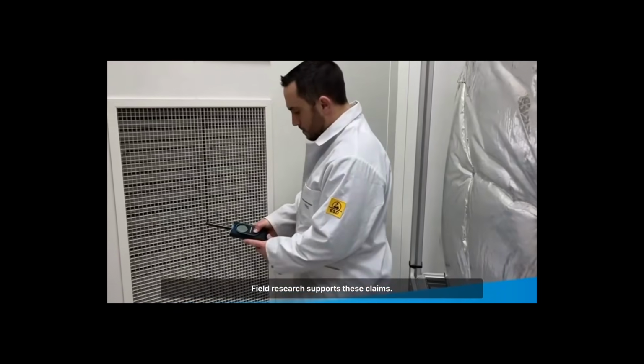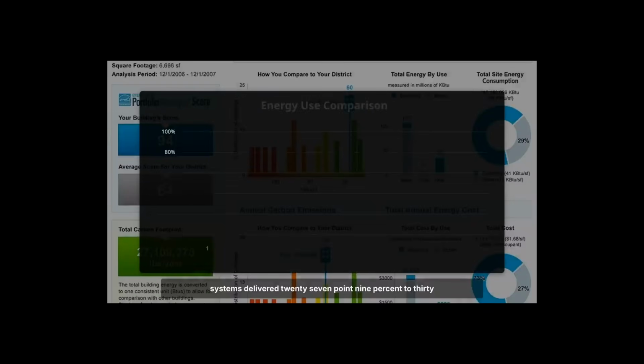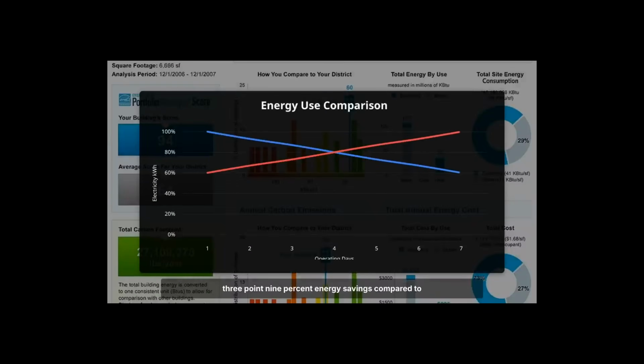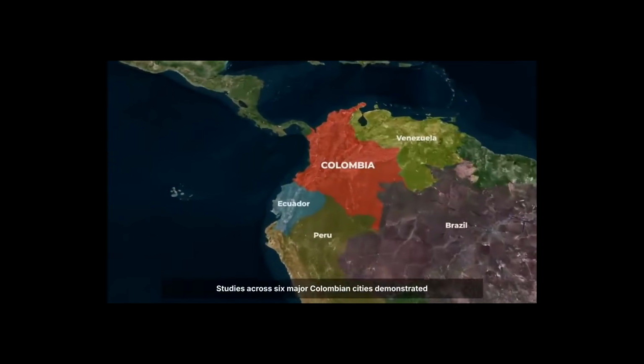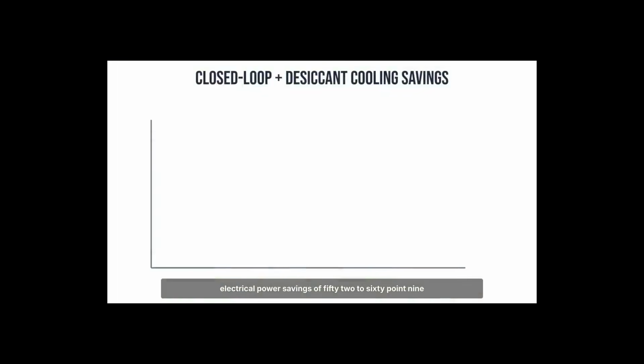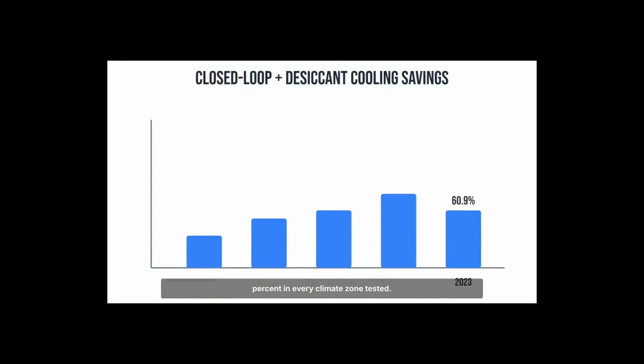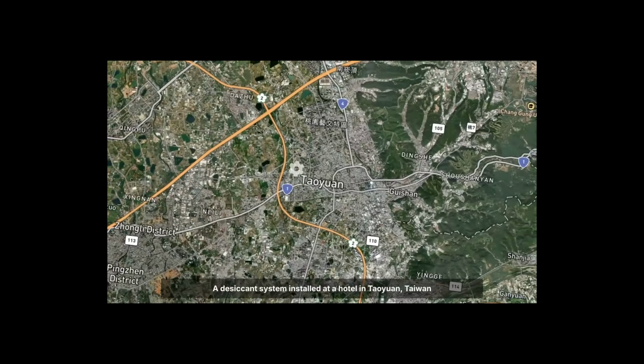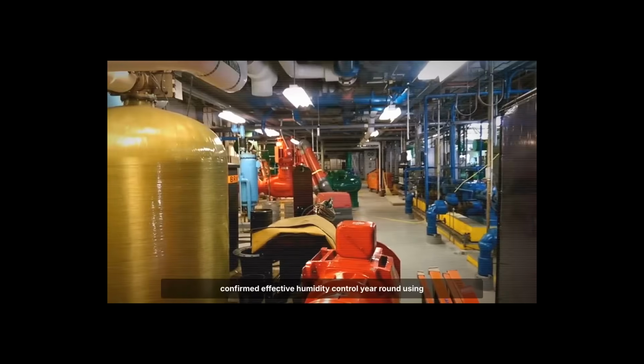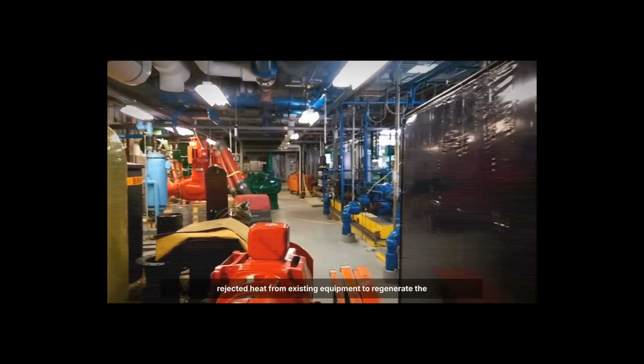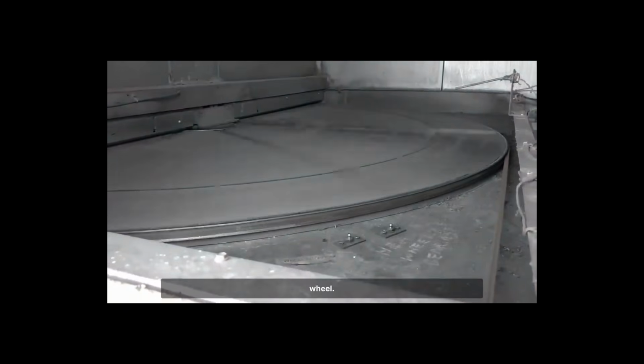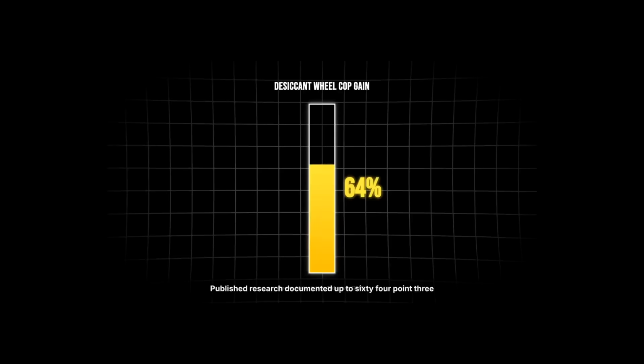Field research supports these claims. In tropical Malaysia, two-stage solar desiccant cooling systems delivered 27.9% to 33.9% energy savings compared to conventional air conditioning. Studies across 6 major Colombian cities demonstrated electrical power savings of 52 to 60.9% in every climate zone tested. A desiccant system installed at a hotel in Taoyuan, Taiwan, confirmed effective humidity control year-round, using rejected heat from existing equipment to regenerate the wheel. Published research documented up to 64.3% increase in coefficient of performance when desiccant wheels were integrated into building climate systems.